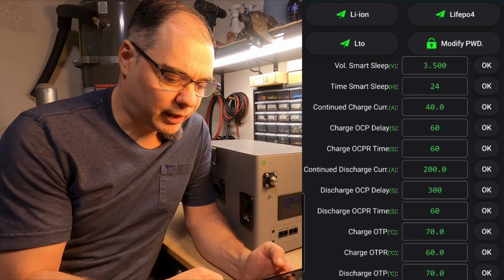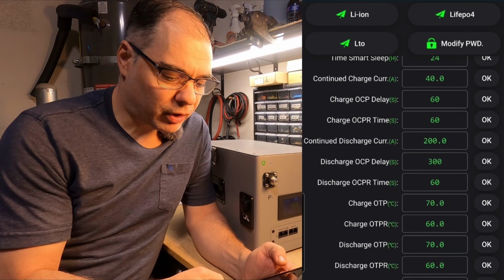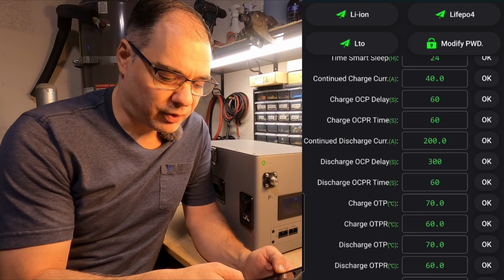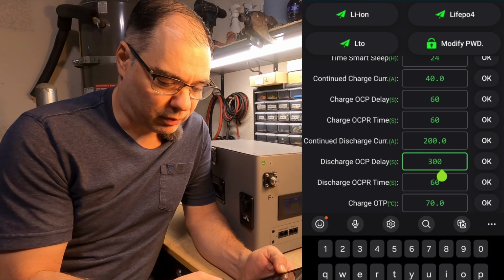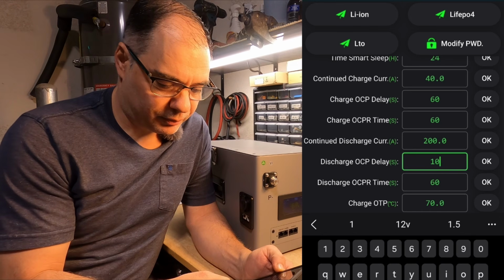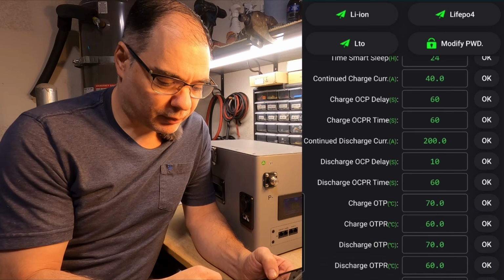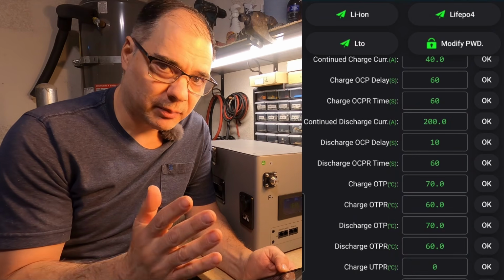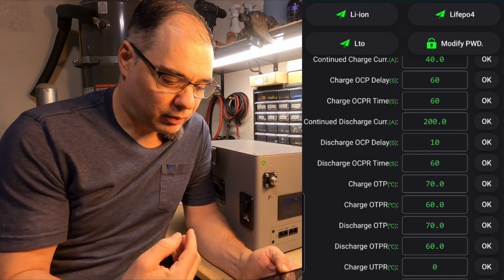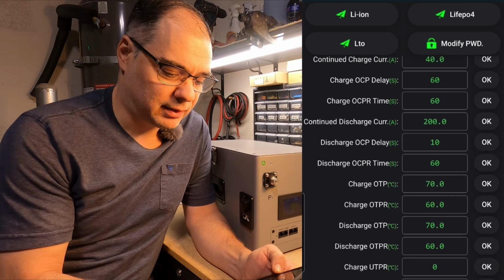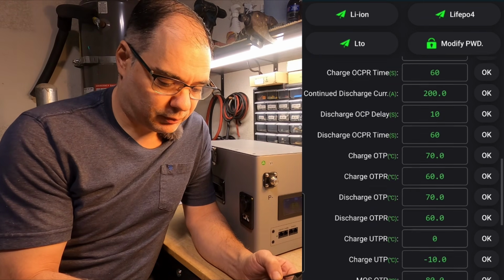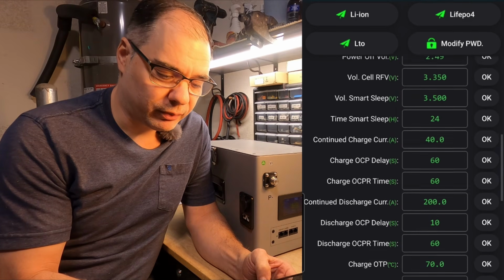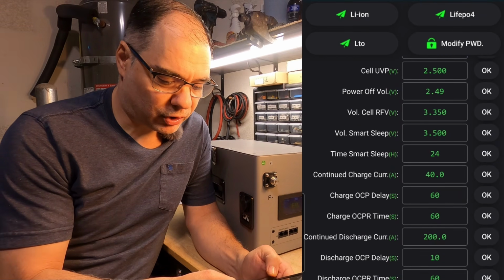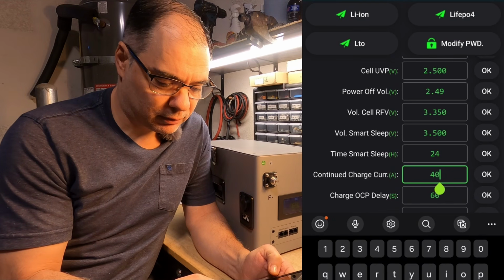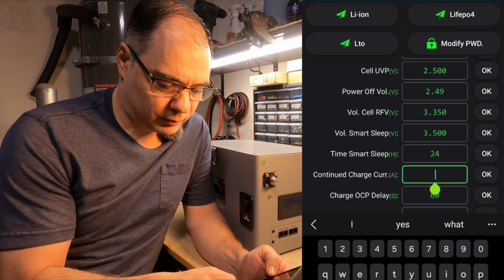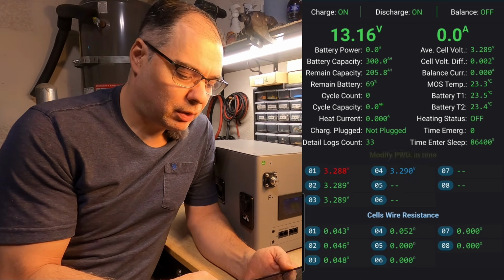Continuous discharge current, 200 amps. Overcurrent protection delay, 300 seconds. That's way too long. Set that for 10 seconds. And then if we hit an OCP, it's going to re-engage the BMS after 60 seconds. That's pretty much the minimum settings that you have to do. Charge current's a little low, we can up that. Okay, we should be good to go.